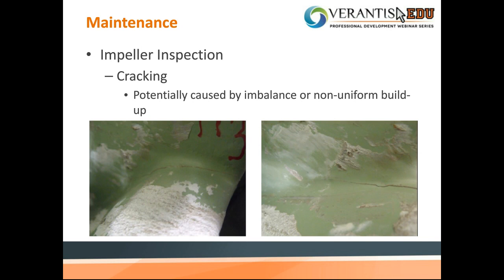And then the last thing you really want to look for is cracking. This is if there is an imbalance due to particulate buildup or some other imbalance, and this impeller has been shaken so much that it can crack. This is considered an impeller failure, and the impeller needs to be replaced and typically can't be salvaged at this point in time.